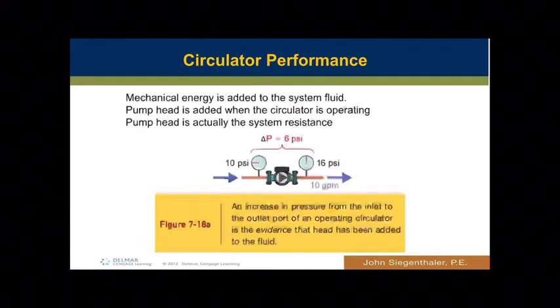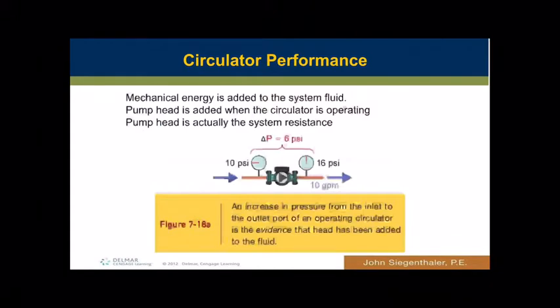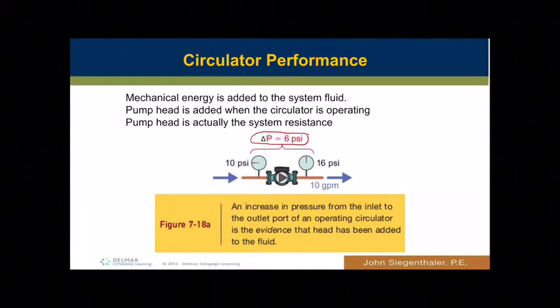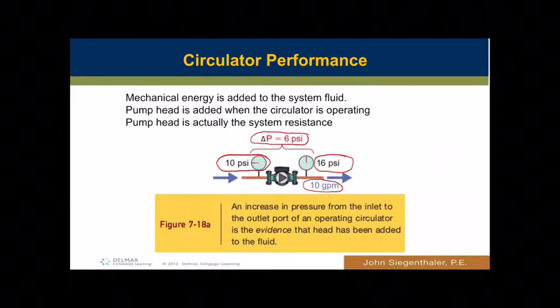The mechanical energy added into the fluid — the pump head being added to overcome system resistance — is what we're looking at. In this picture, I've got a pressure delta P of 6 PSI across the pump: 16 PSI on the discharge side and 10 PSI on the inlet side. The amount of energy or pressure being added is 6 PSI.